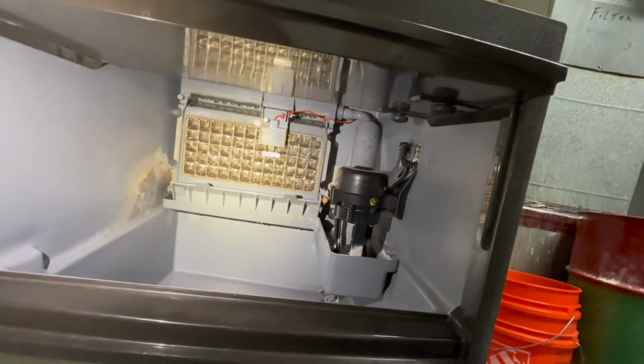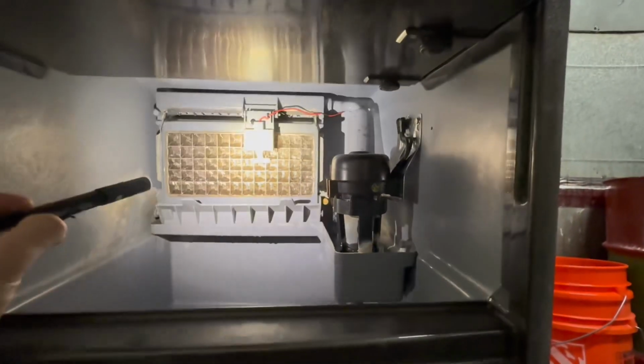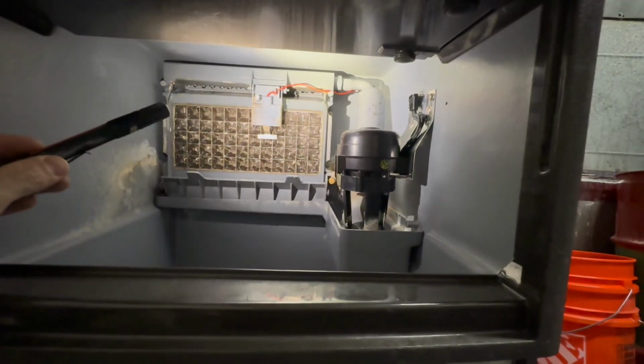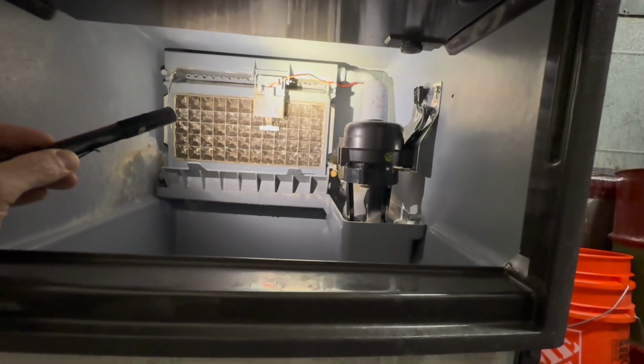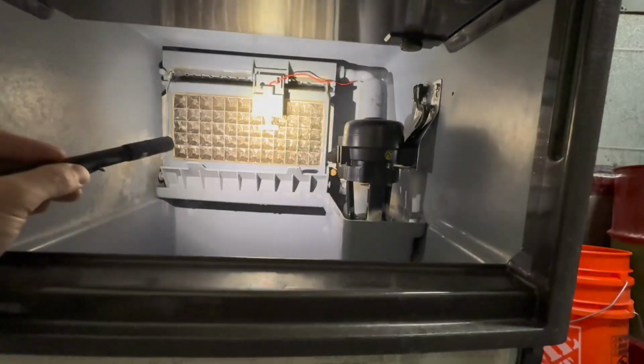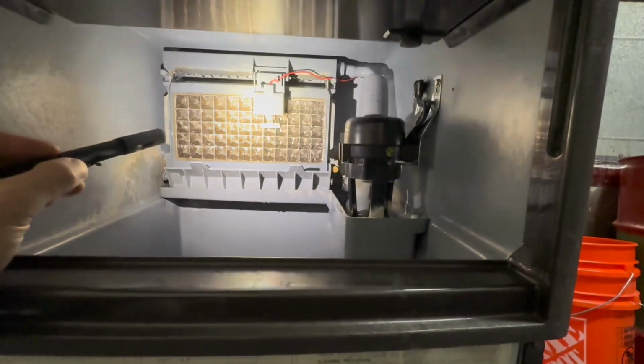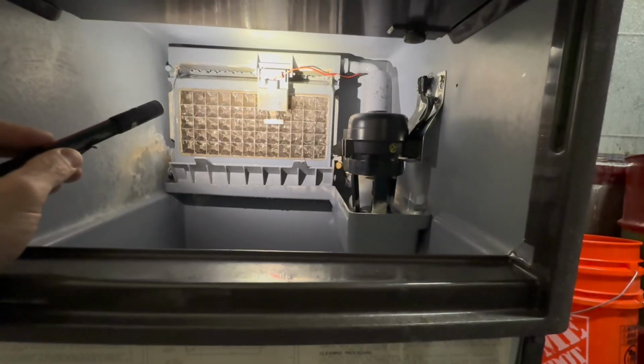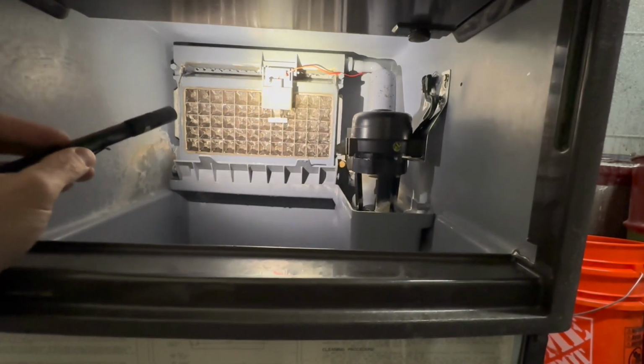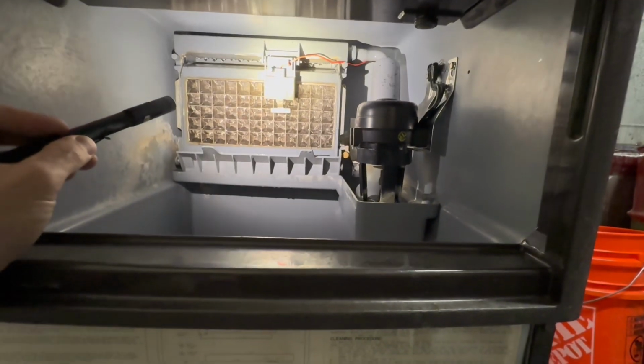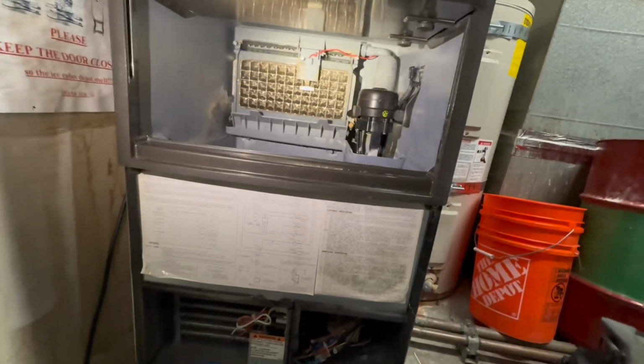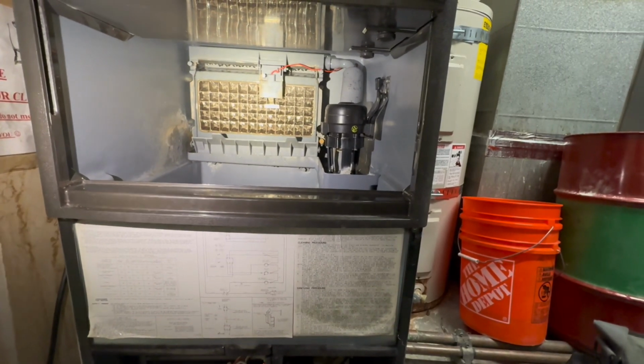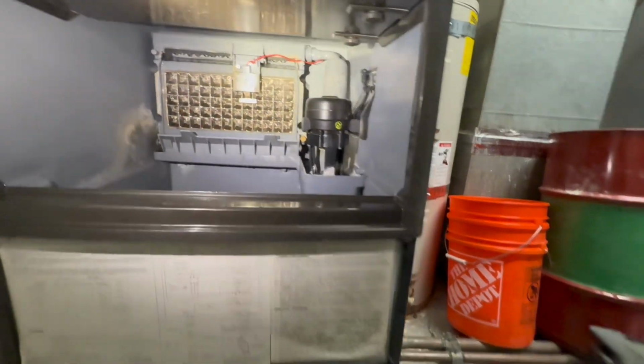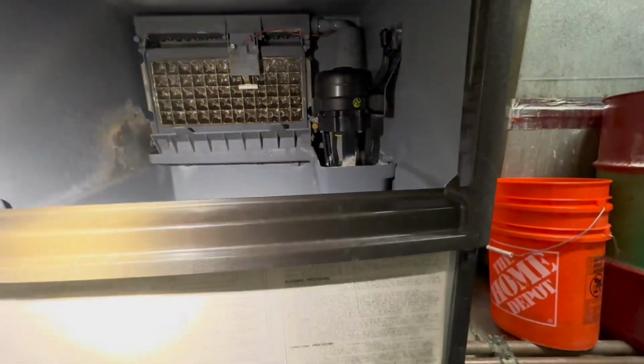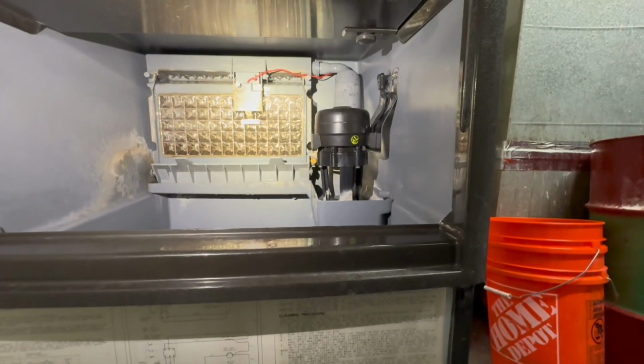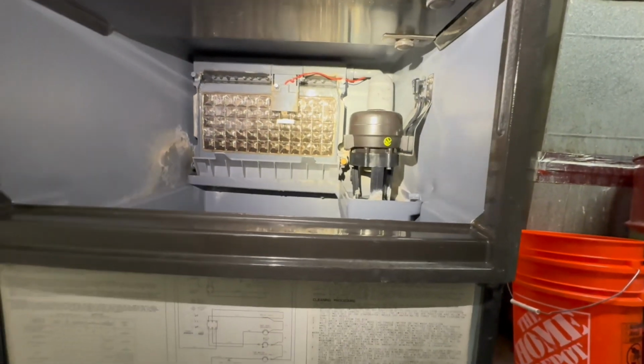I'm convinced possibly that my ice thickness probe is dirty. It's getting wet and then grounding itself out, and the machine is cycling into harvest before there's enough ice formed on the evaporator. And that's possibly why it's going into harvest, or it's going off on long harvest. The reason being that it's going into harvest prematurely before there's enough ice on the evaporator. So that's a possibility. I might recommend that they change the ice thickness probe just as a precaution. I could try cleaning it, but I don't think it's going to get much better.